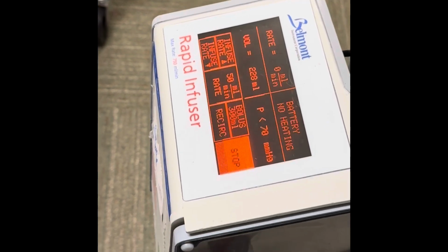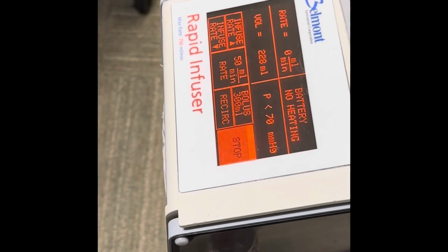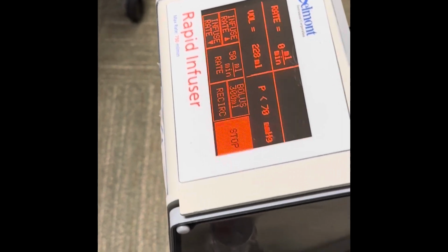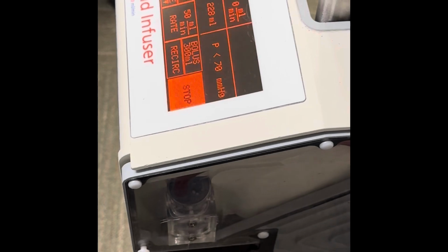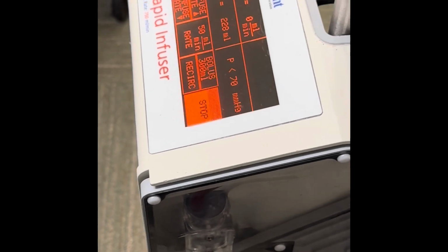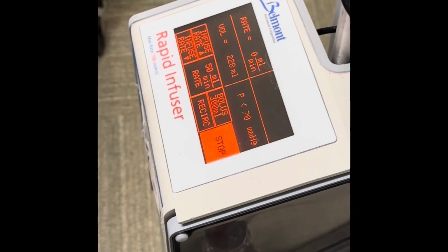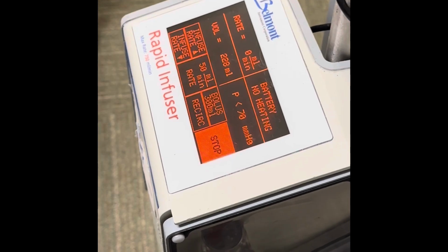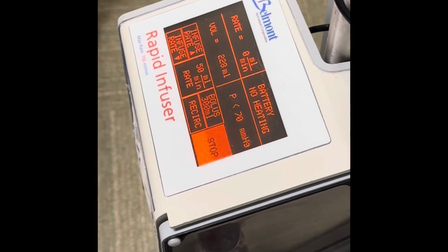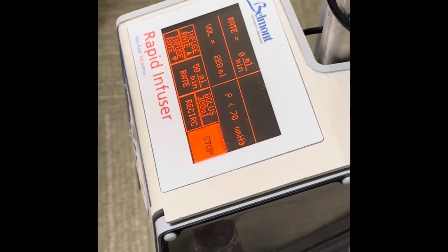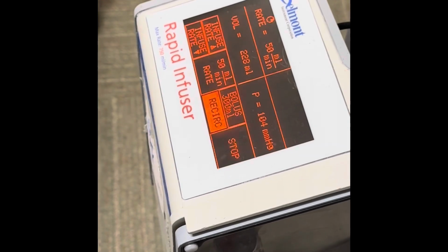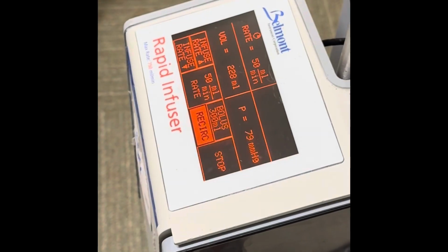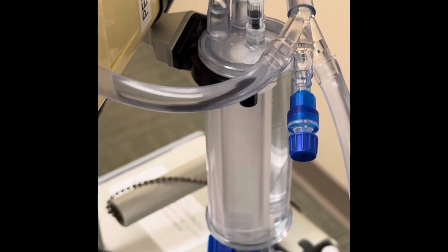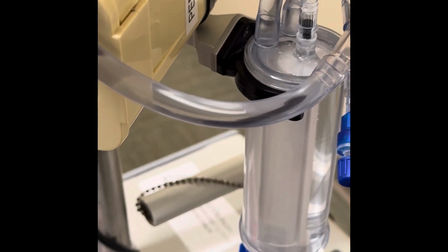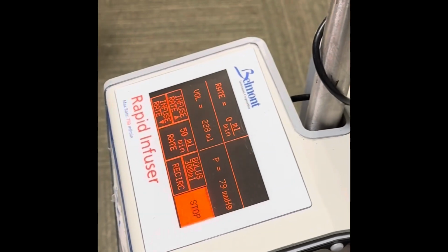If you need to adjust the bubbler, give it a squeeze and reseat it so the sensor can evaluate it. If you've given a significant amount of blood products and notice it's bogging down, you can hit the recirculation button and it will recirculate everything in your chamber, then stop that when you feel it's appropriate. Hit stop and then you can start reinfusing.